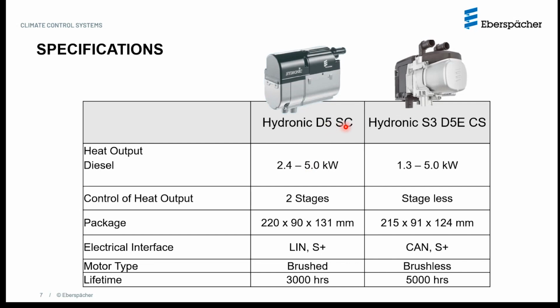What follows next is an abbreviation for describing the assembly itself. So this is a standard compact heater, and it's described as such because the coolant pump is part of the entire heater assembly. So let's say if you had to service the coolant pump, you had to clean out the coolant pump, then you would have to pull out the whole unit and then tear it down and then service the pump, for example. Whereas in case of the Hydronic S3, the nomenclature is slightly longer. It says Hydronic S3. S is defining the size of the heater. So we have the Hydronic available in 3 different sizes, the small, the medium, and the large. So this falls into the small category.